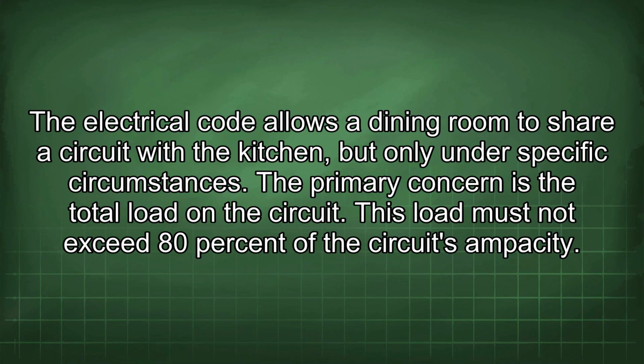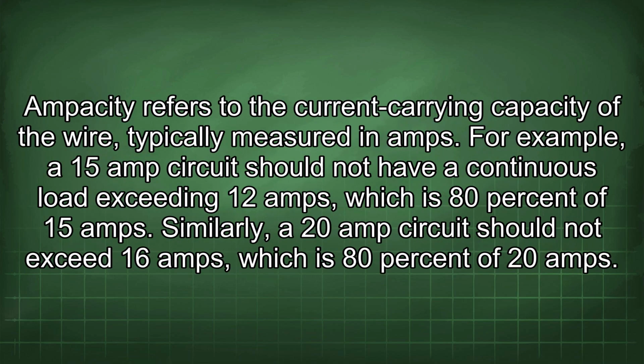The electrical code allows a dining room to share a circuit with the kitchen, but only under specific circumstances. The primary concern is the total load on the circuit. This load must not exceed 80% of the circuit's ampacity. Ampacity refers to the current carrying capacity of the wire, typically measured in amps. For example, a 15 amp circuit should not have a continuous load exceeding 12 amps, which is 80% of 15 amps. Similarly, a 20 amp circuit should not exceed 16 amps, which is 80% of 20 amps.